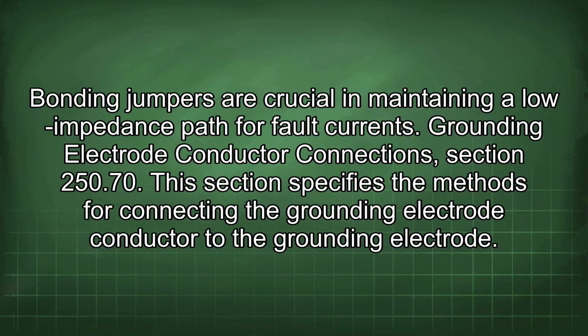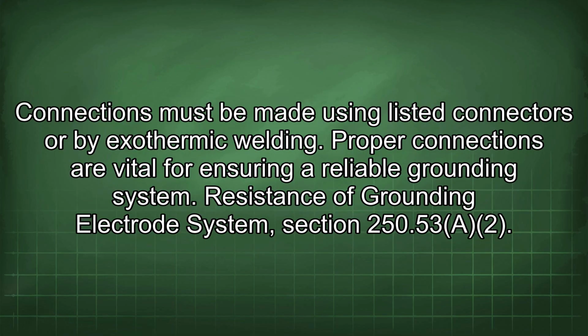Grounding electrode conductor connections, section 250.70. This section specifies the methods for connecting the grounding electrode conductor to the grounding electrode. Connections must be made using listed connectors or by exothermic welding. Proper connections are vital for ensuring a reliable grounding system.